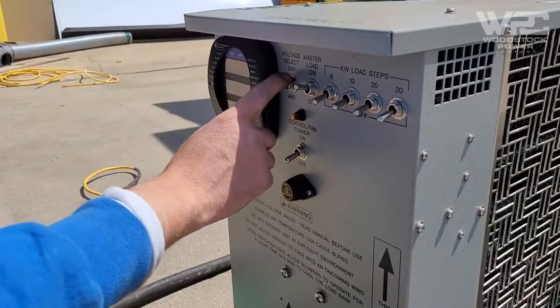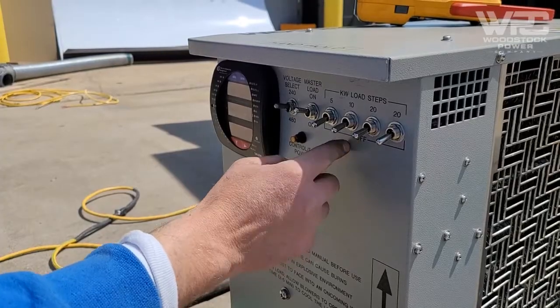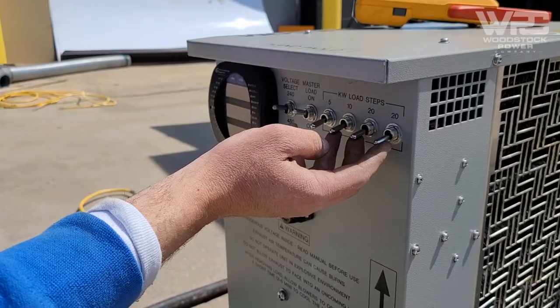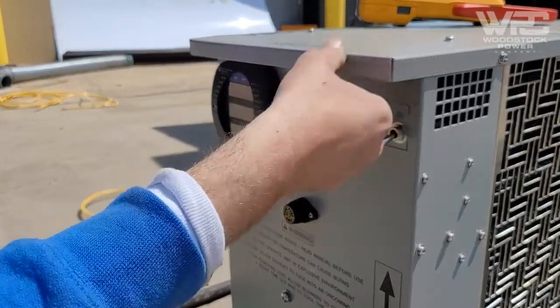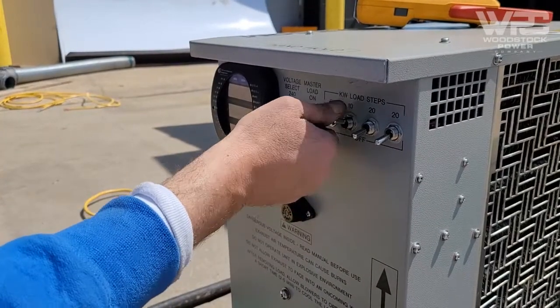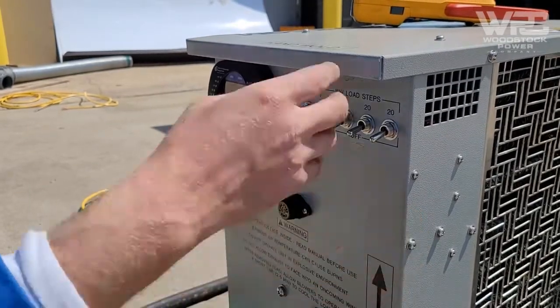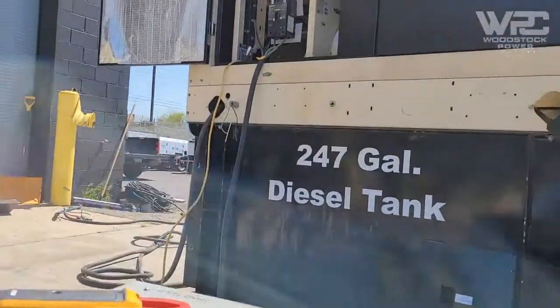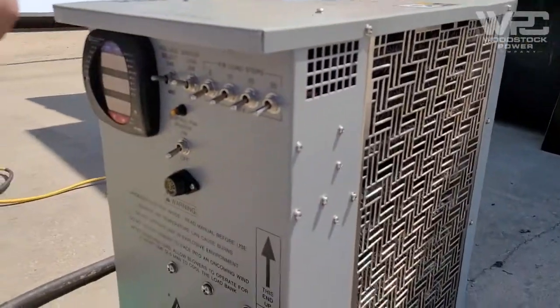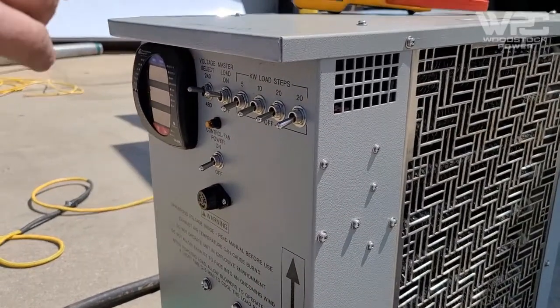This load bank is rated at 55kW and we're testing at 120/240V. We won't be using all of its steps — we'll use combinations of the 20kW, 20kW, 10kW, and 5kW steps to achieve 25% and 50% load. One very important thing: always make sure the generator itself is grounded as well.